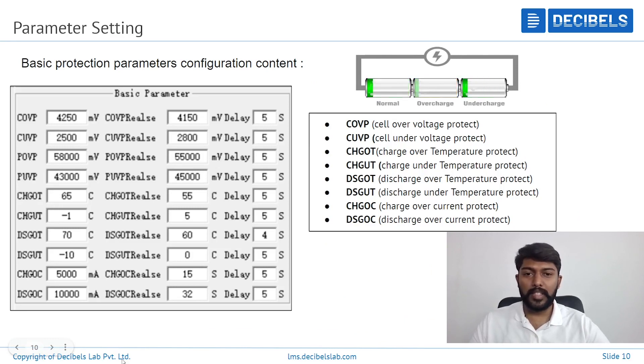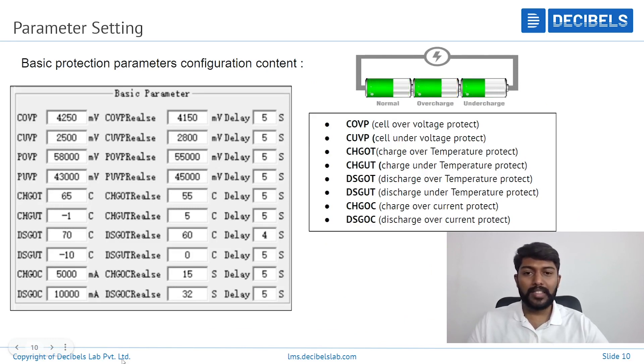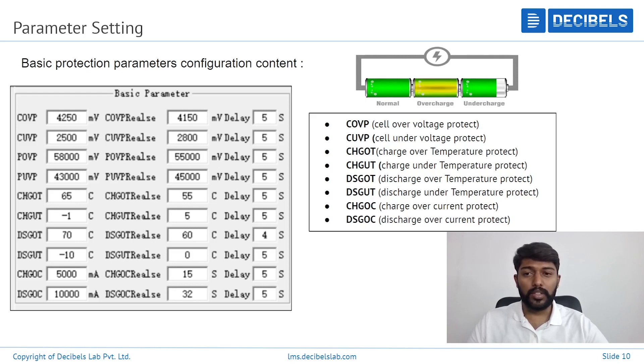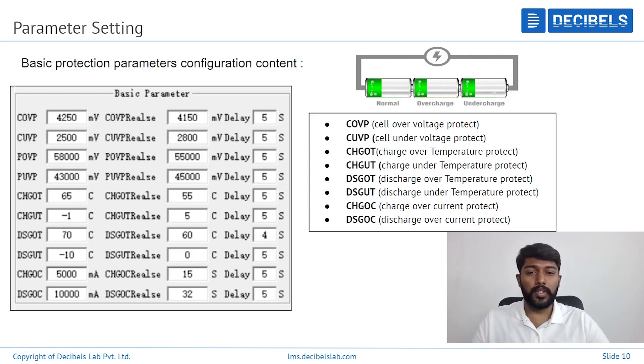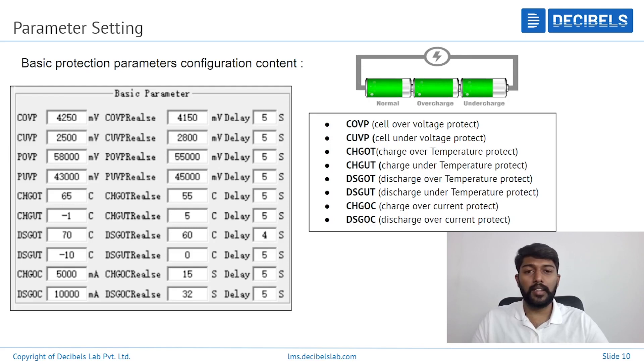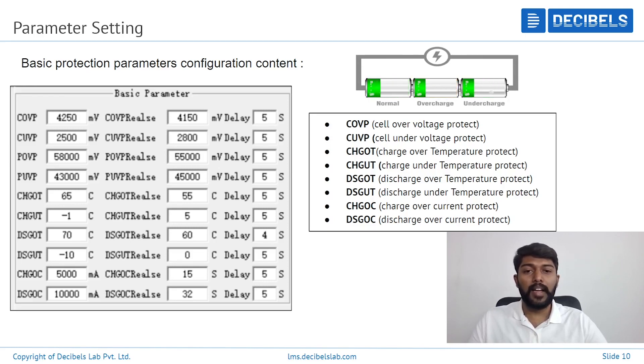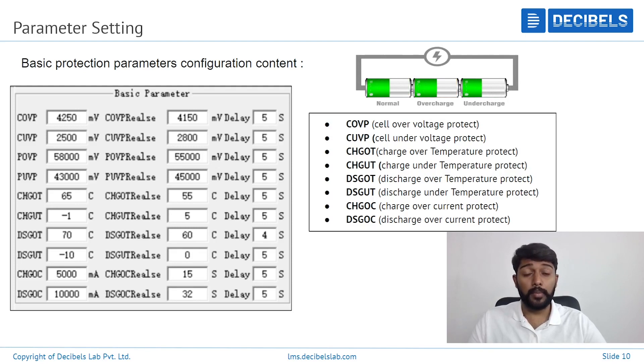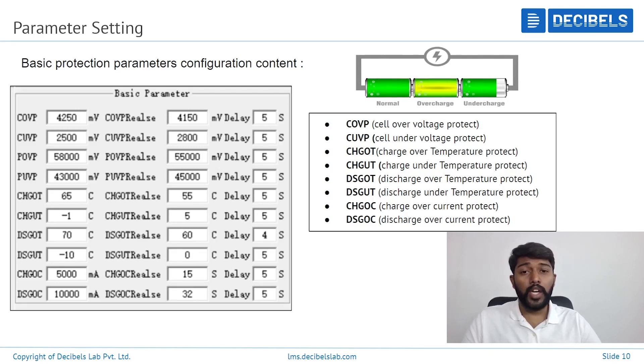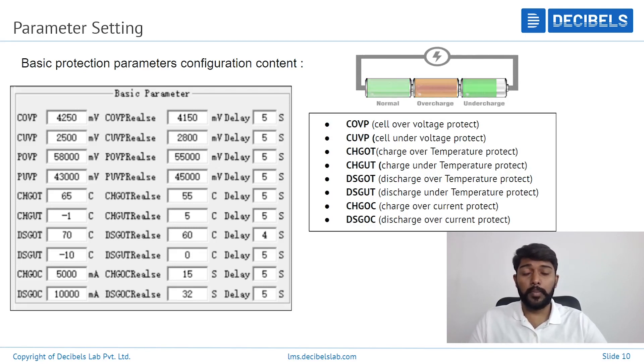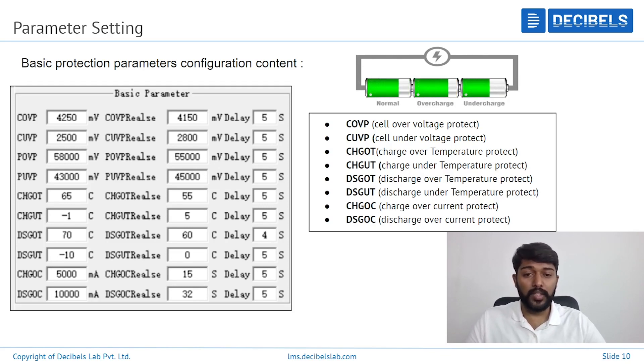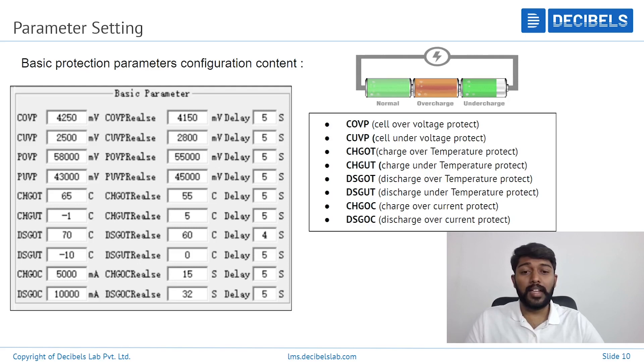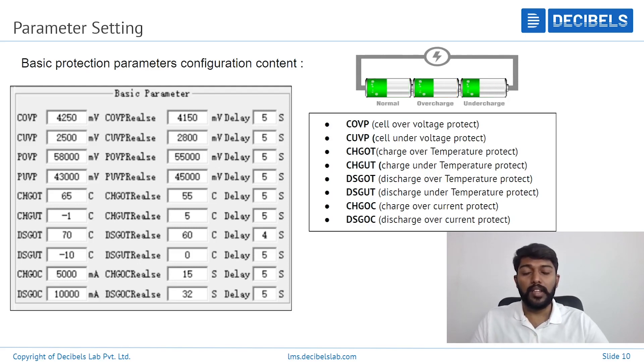Here we can see the parameter setting. I'll just go one by one. COVP stands for cell overvoltage protection - basically any cell above the limits of the voltage, the protection will start. Undervoltage protection you have similarly. Then you have charge over temperature protection, charge under temperature protection, discharge over temperature protection and discharge under temperature protection. Then you have charge over current protection and discharge over current protection. These are the basic parameters.